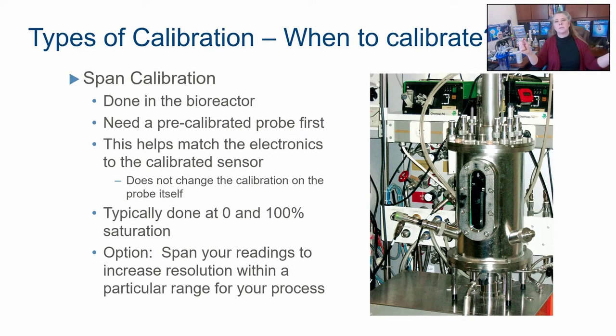And the way you do this, there's two possible ways. It doesn't really matter which way you do it as long as the policy is set and everybody does it the same way. Okay. You sparge with a specific sparger at a specific stir rate, at a specific gas flow rate, 5 liters per minute or whatever. Okay, consistent. For some period of time, you've decided for a 1 liter reaction with this certain media, it should only take 20 minutes to sparge all the oxygen out. And you say, okay, I'm at zero. There's my zero cal.